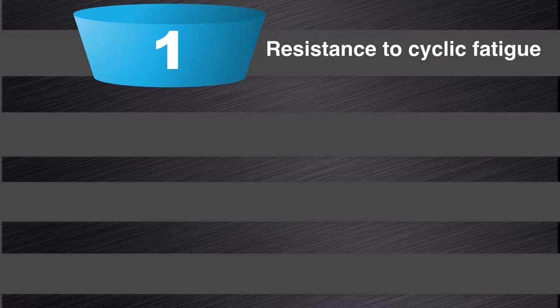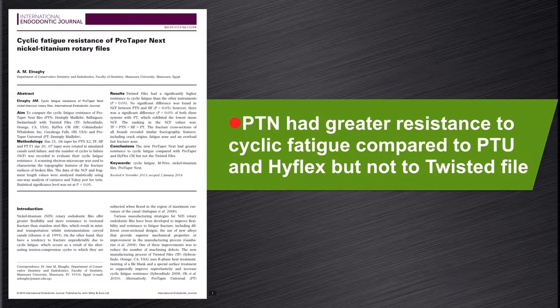The first aspect I want to look at is the resistance to cyclic fatigue. In this study by Elnaghy in 2014, he looked at cyclic fatigue resistance of ProTaper NEXT NiTi rotary instruments. He concluded that ProTaper NEXT had a greater resistance to cyclic fatigue compared to ProTaper Universal and the HyFlex instruments, but not to the twisted file system.